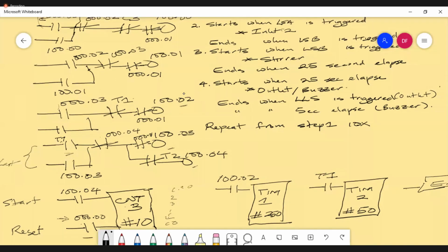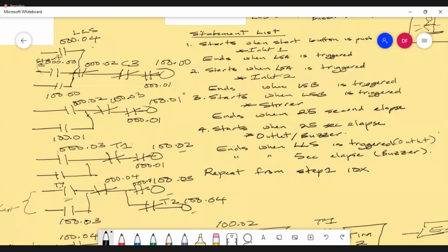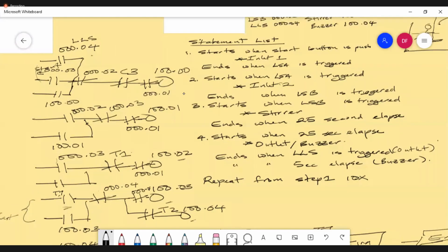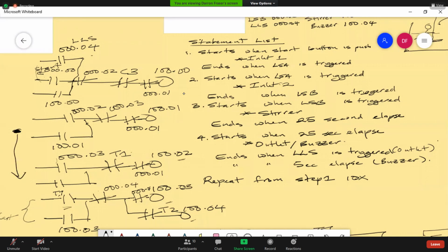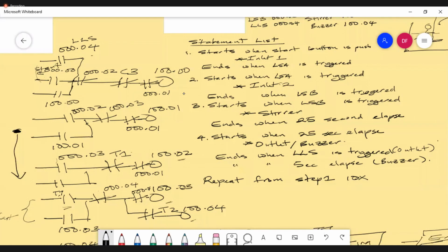All right. So now, the stop is in every line because it's a safety device. So somebody drops in the mixing tank and you want to stop it, and let us say that you're at this point in the program, because the program is running sequentially. Let me digress. Ladder logic programs don't necessarily run sequentially. We have written it sequentially. That is why it is running sequentially. Any line that you trigger, that is what works. But we have written it so it runs from line 1 to line 2 to line 3 to line 4.